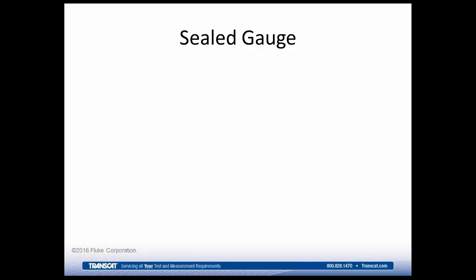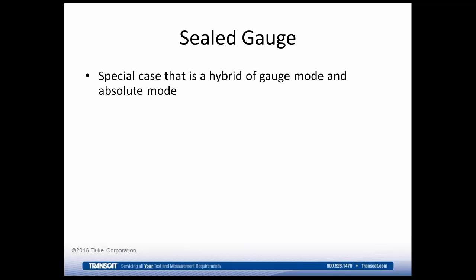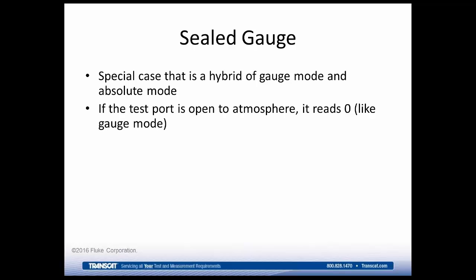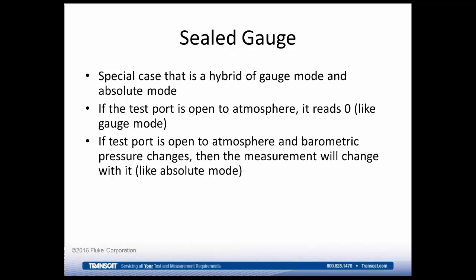There's also a term called sealed gauge. And what does that mean? It's kind of a hybrid of gauge mode and absolute mode. In this case, if the test port is open to atmosphere, it reads 0, just like a gauge mode device. But if the barometric pressure changes, then the measurement will change with it, like an absolute mode device.